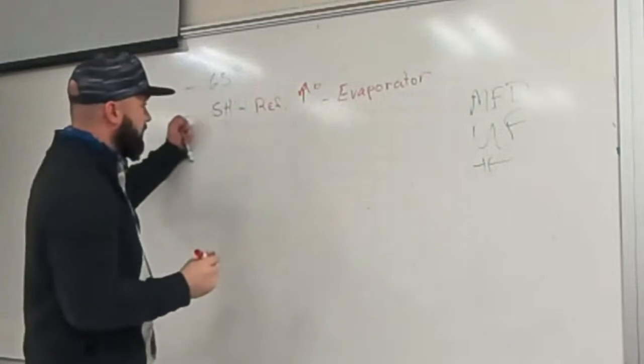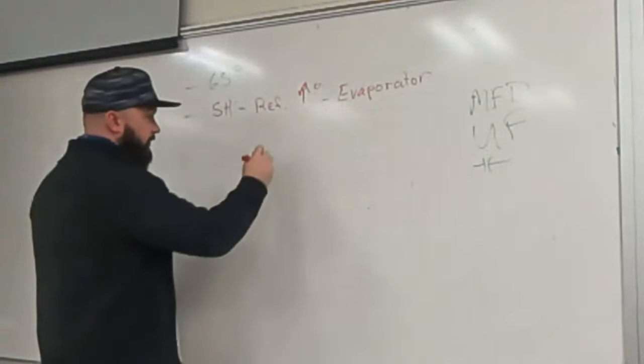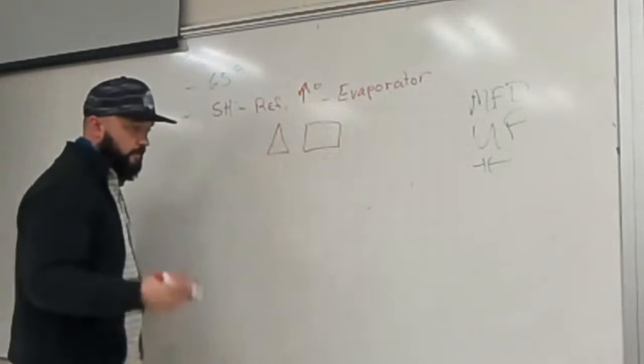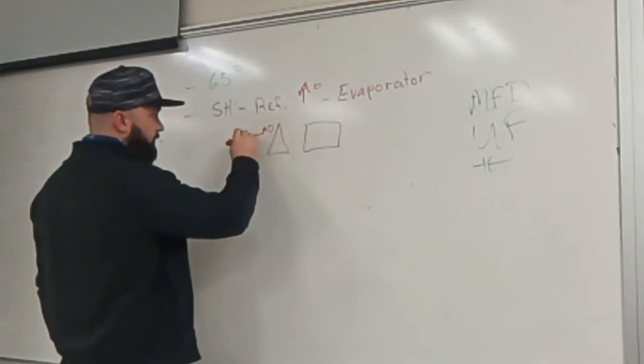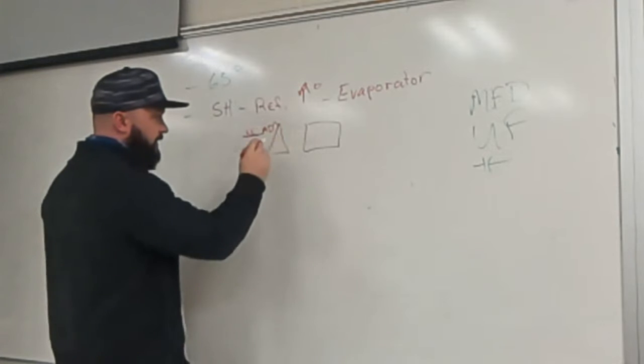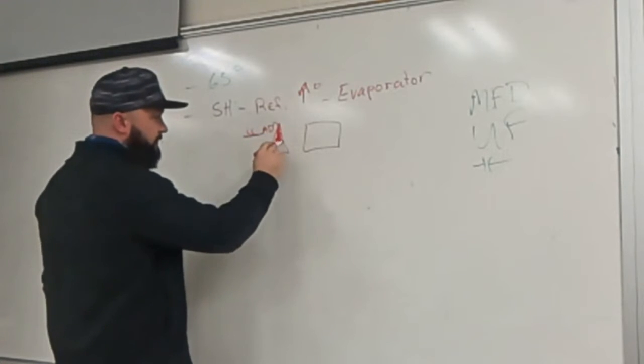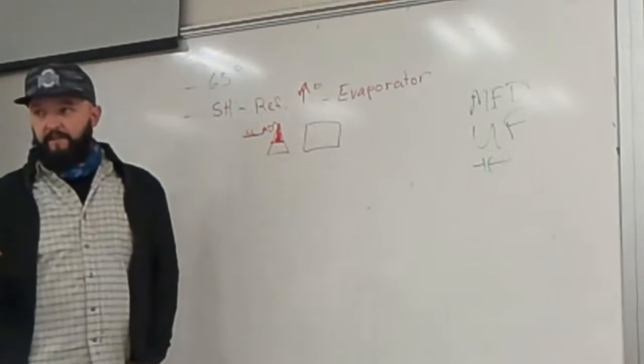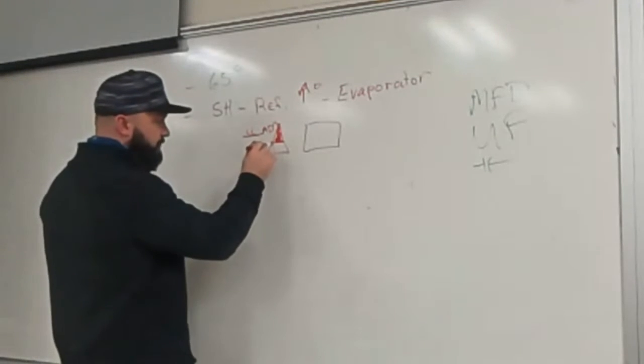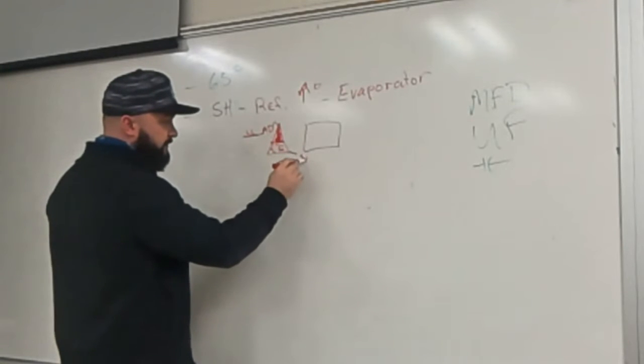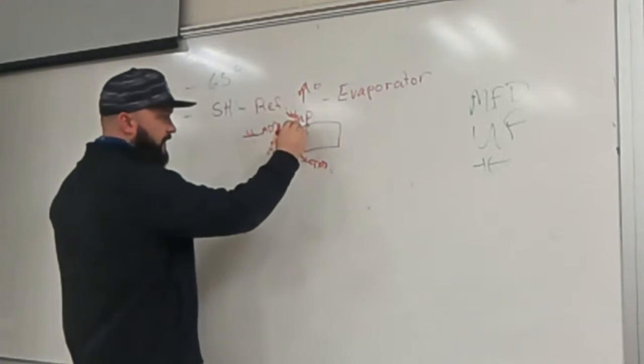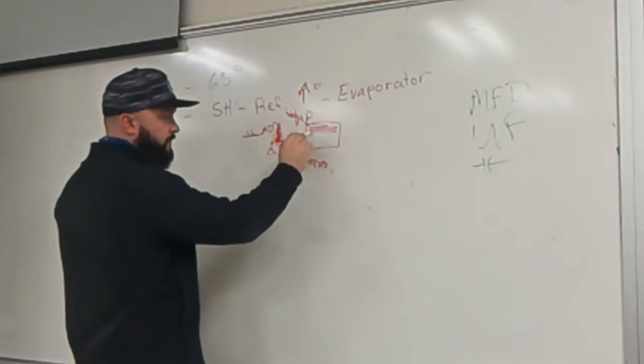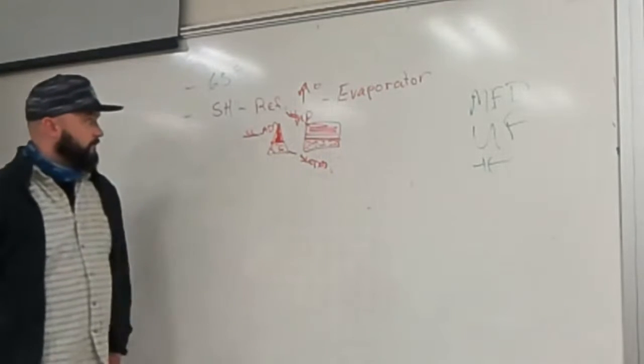Very quickly: you've got an A-coil or a refrigeration coil. It hits the metering device coming from the liquid line — so this is your liquid line — then it drops in pressure greatly and comes in as a liquid. About halfway or a little past halfway through that coil it absorbs enough heat to boil off and turn into a gas, then it comes out on your suction line.